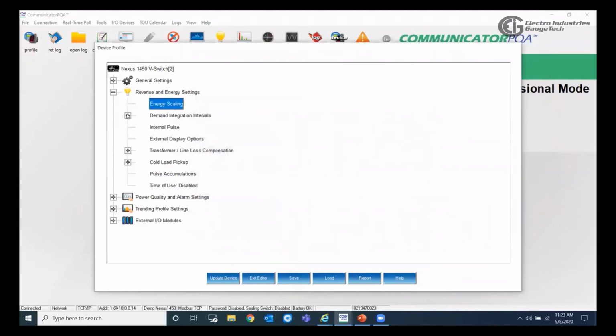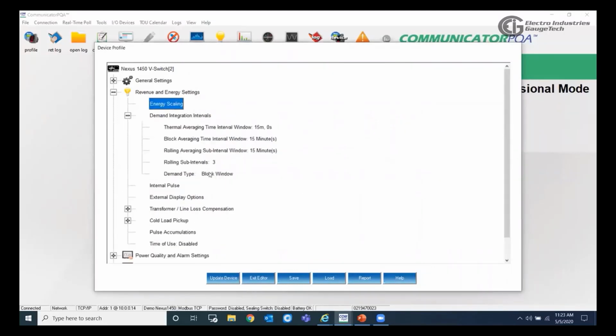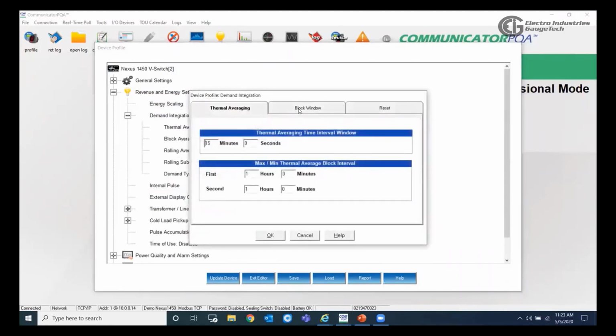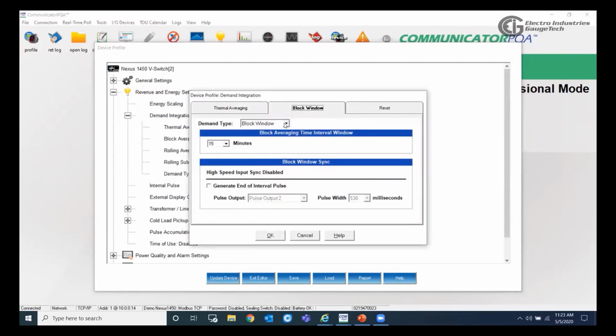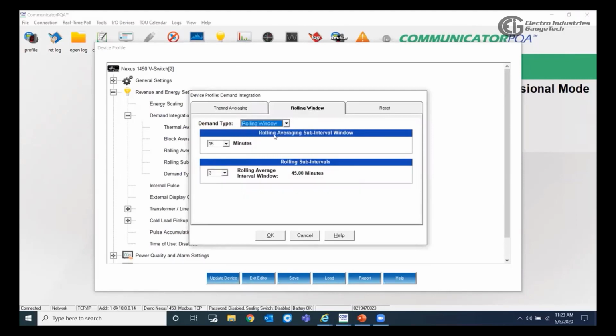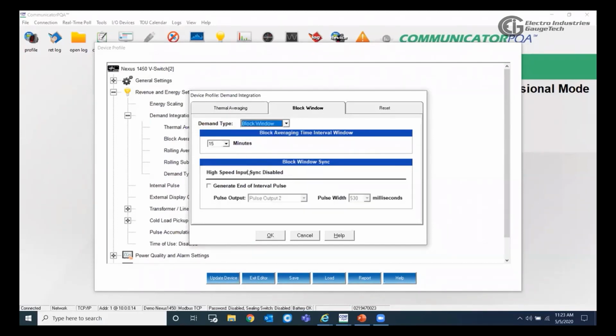The demand integration interval, this is where we can set what kind of demand, by going to the block window here, and we can choose between the block or the rolling. And we can also set the interval, like is it every 15 minutes or 10 minutes, and the sub interval for the rolling only. If it's block, there will not be that option.